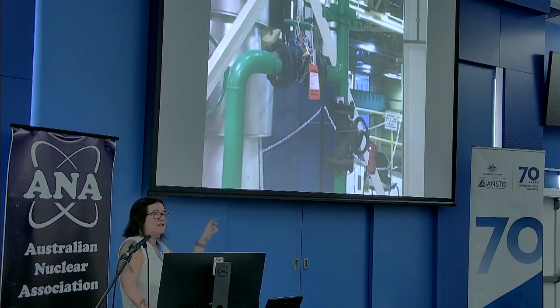So we went in, found the leak, and closed the isolation valves. It was a pipe that had actually broken, so it needed a manual intervention. The interesting thing was, on the secondary side, because there was so much extra heat created, the condenser tank overfilled, and it was actually raining in the stairway. As we walked up to the boiler room, it was light water - there was no danger. But it just shows you how everything's interconnected from the reactor side to the turbine side, and you have to understand that interconnection to understand the hazards and the diagnosis.